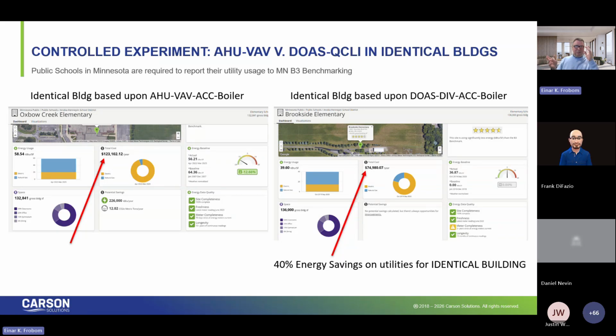Why wouldn't we do this? I mean, this makes no sense. Why do we see the savings? And it's not just one big cut. The biggest cut is over here. This is moving a whole lot of air that's wasted. Air is not an effective heat transfer medium. Water is much more effective in terms of addressing BTUs in a system. The smaller DOAS unit, the smaller air-cooled condensing unit, the application of displacement induction, all of these layers add up to this savings. That's $50,000 times 25 to 30 years for two comparable buildings.